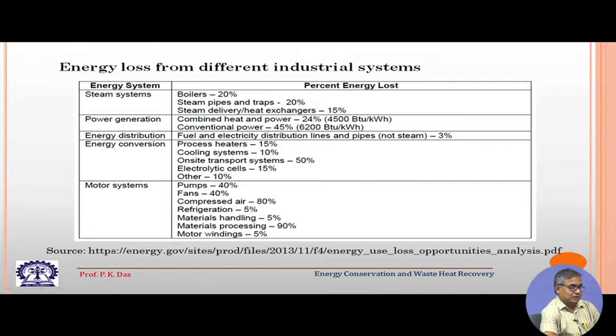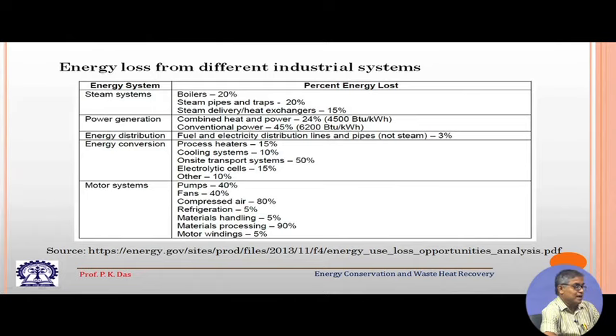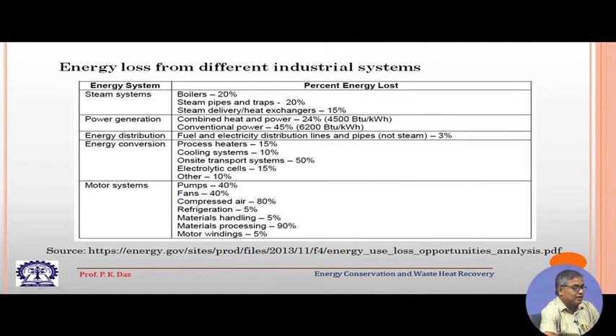Steam delivery exchangers — wherever there is any heat exchange process involving steam — that also constitutes around 15 percent. Then we come to power generation. This will be elaborated in the following lectures as it could be combined heat and power. If we have the option for generating both heat and power, the losses are around 24 to 25 percent. For conventional power, that is around 45 percent energy loss which can be recovered. These are estimates based on surveys of different industries, and for a specific industry these values may differ slightly.